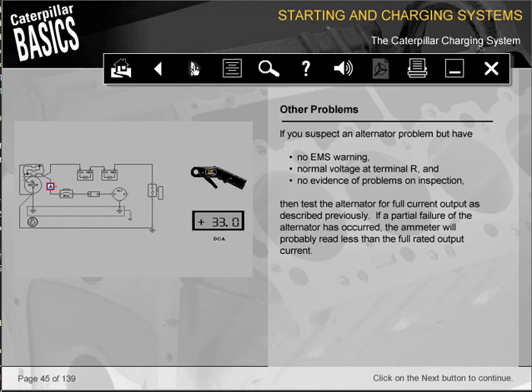If you suspect an alternator problem but have no EMS warning, normal voltage at terminal R, and no evidence of problems on inspection, then test the alternator for full current output as described previously. If a partial failure of the alternator has occurred, the ammeter will probably read less than the full rated output current.